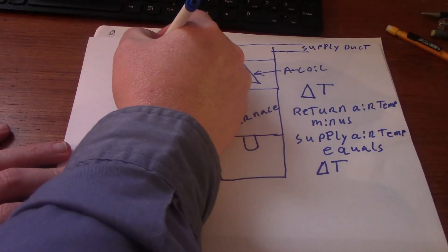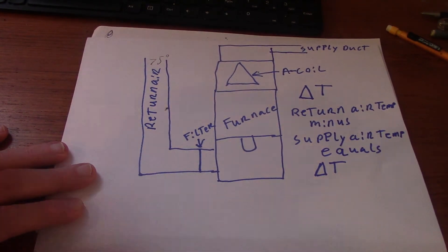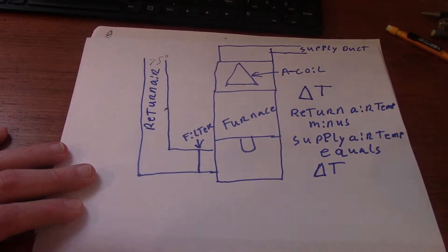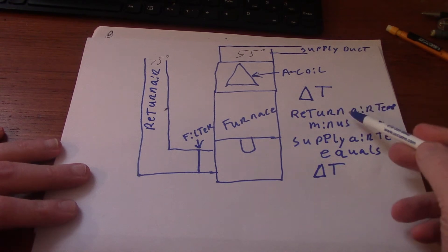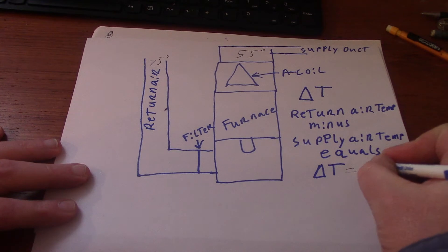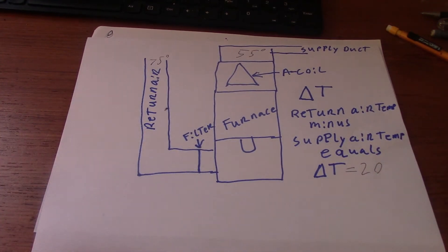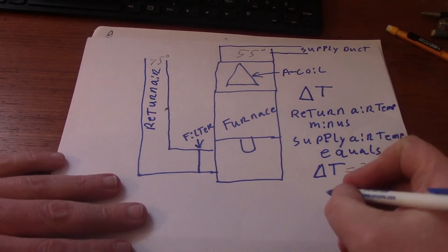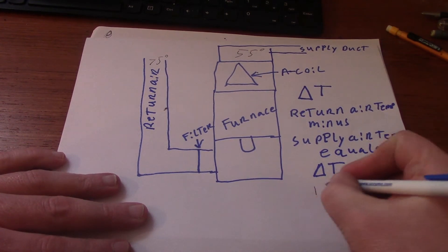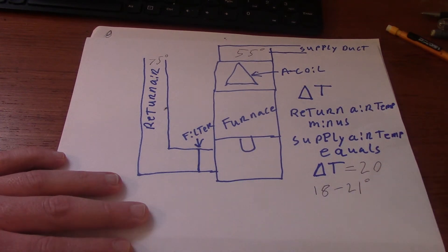Return air temperature will say 75 degrees. Your supply air temperature, in ideal situations, would be 55 degrees. So 75 minus 55 will equal Delta T. Our Delta T is right now 20. 20 is a nice perfect number. It's what I was always taught in school because it's easy to remember. There is a range that you can have, 18 to 21 degrees for your Delta T.